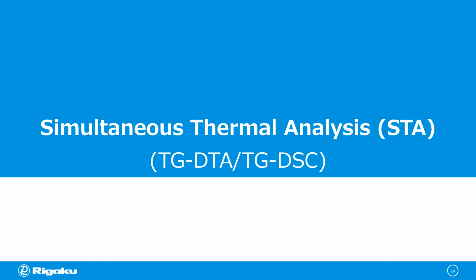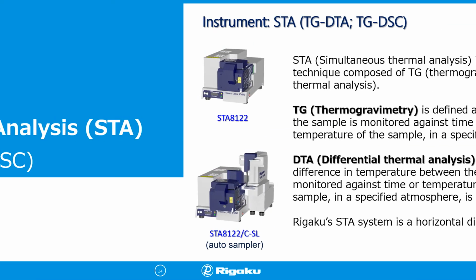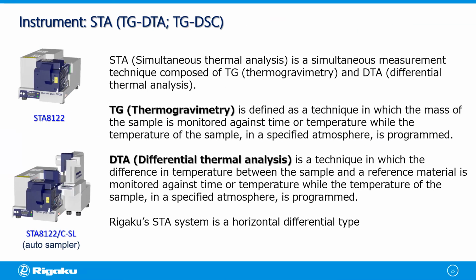From this slide onwards, we will be talking about simultaneous thermal analysis. Simultaneous thermal analysis, or STA, is a simultaneous measurement technique composed of thermogravimetry, or TG, and differential thermal analysis, or DTA.